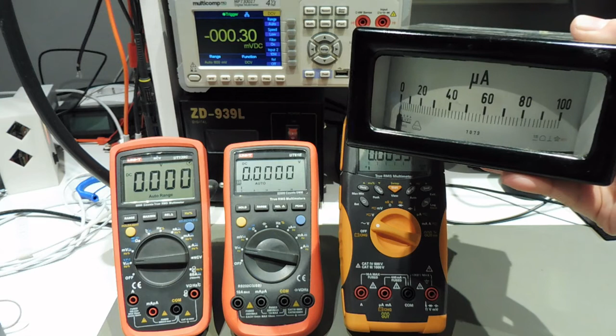I already mentioned that 0.1% figure. I recall that this analog meter has an accuracy of 1.5%, which means that when it shows 100 microamps, right at full scale of the range, it might actually be just 99 microamps and still be within specification.